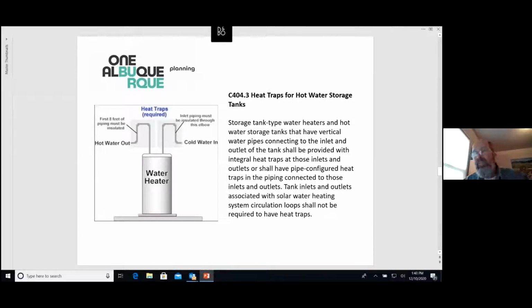So heat traps for hot water storage tanks. Now, a lot of water tanks, hot water tanks, storage tanks, water heaters in essence, have these built into them. If they don't have an integral heat trap, one will have to be piped in, and the picture here illustrates how that works. Basically, it's to keep it from siphoning out and transferring across. So should you need to pipe one in, this is basically what it looks like. As a plumber, I haven't seen one in a long time.